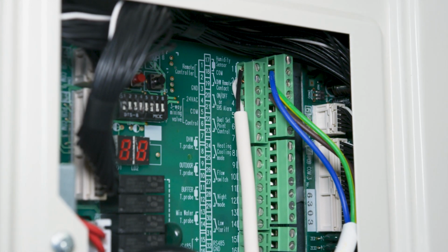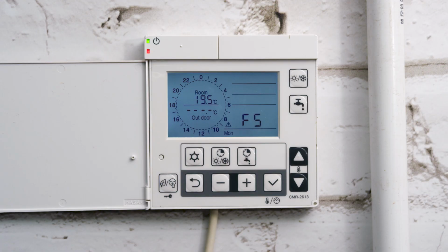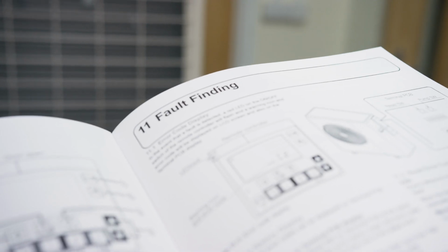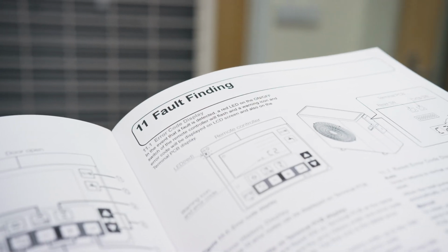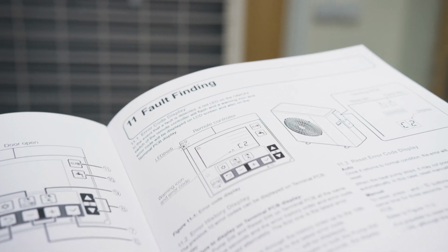In the event of an error occurring, this will be displayed in one of two areas. Let's go through them together. The first is on the terminal PCB on the heat pump and on the controller. The controller on-off switch LED will flash red if there is an issue, along with displaying both a warning icon on the LCD display and a two-digit error code. A full list of fault codes can be found in the relevant section of the installation instructions.